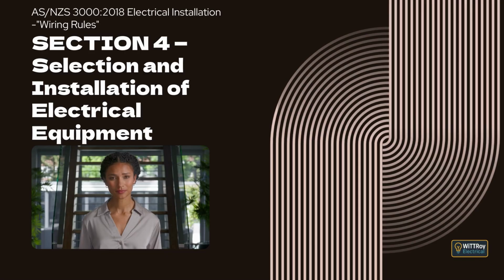Clause 4.12.5.2 Circuit protection. Clause 4.12.5.2.1 General. This clause explains that every submain or final subcircuit supplied from an electricity converter must be individually protected and must include additional protection where required.